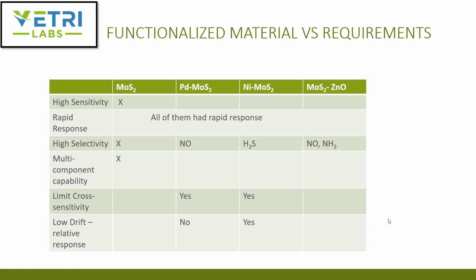Moly sulfide had multi-component capability, but once you start getting into multi-component capability, there is cross-sensitivity. So you have to be careful about needing multi-component capability. In automotive devices where they look at average exhaust, multi-component capability is good enough. But for a biomarker application, you need high selectivity without any cross-sensitivity.